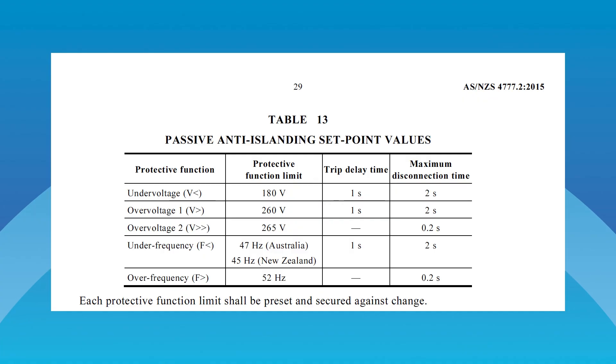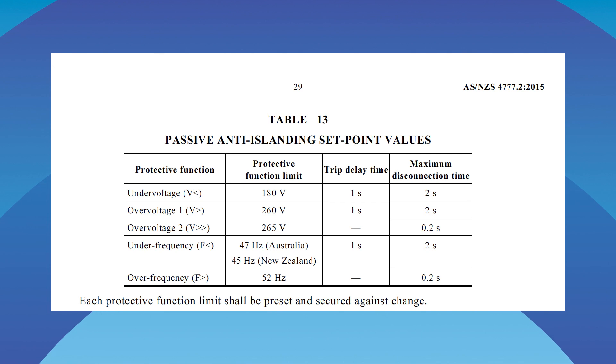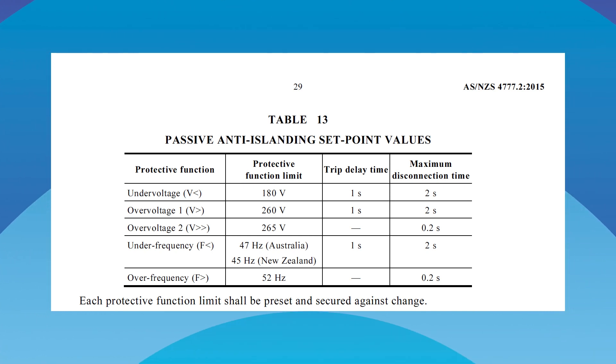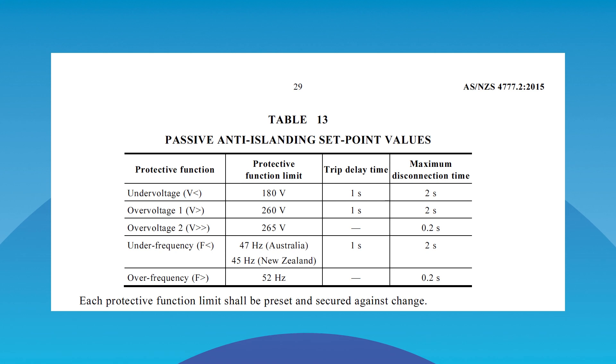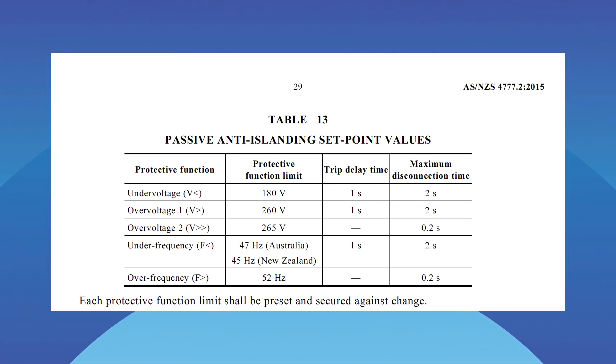SA Power Networks, our local DNSP — distribution network service provider — decided they needed to shut down more solar systems than they could with the special remote shutdown system. So they went to a bunch of substations and ramped up the voltage. Australian standard AS4777.2 says if the voltage gets too high, all inverters have to shut off. So if you were on one of those substations, your inverter had to shut off when it saw the high voltage, whether you've got remote shutdown installed or not.